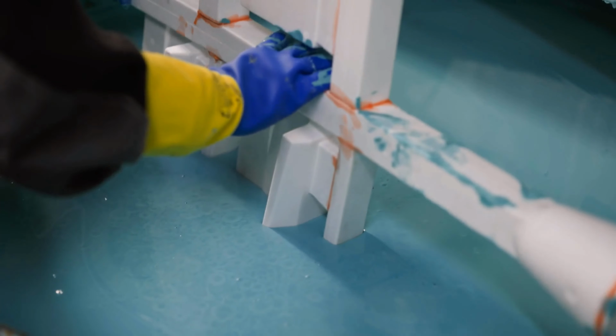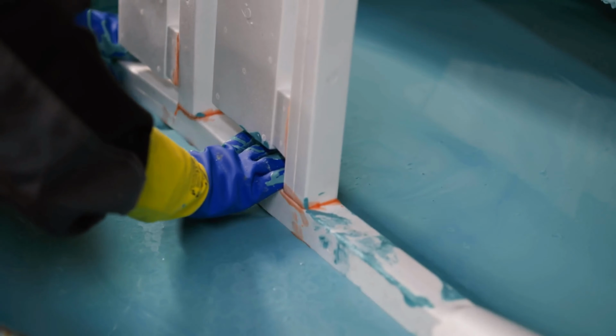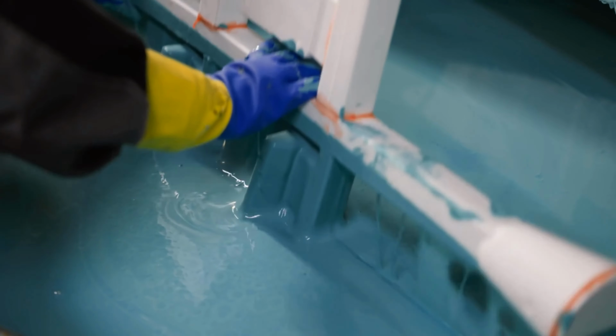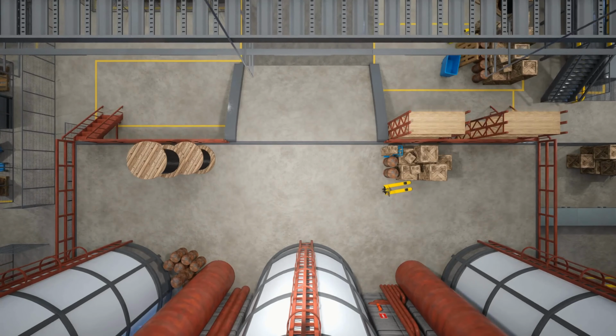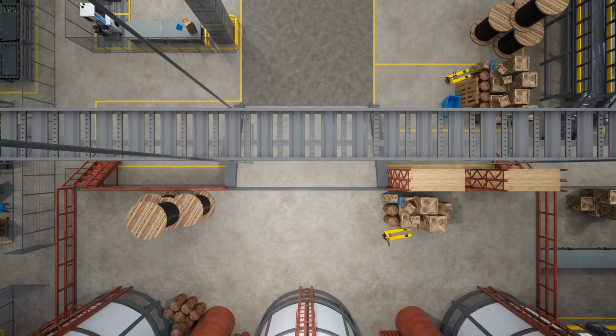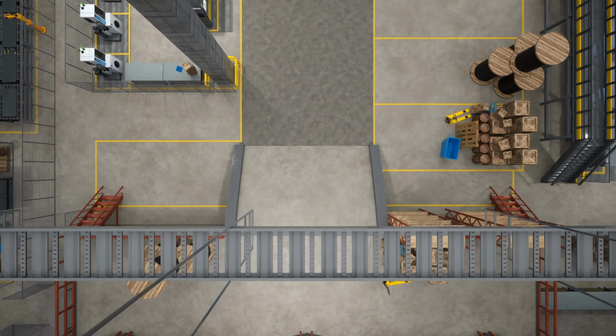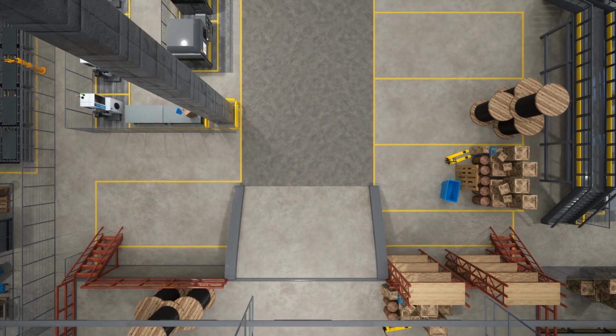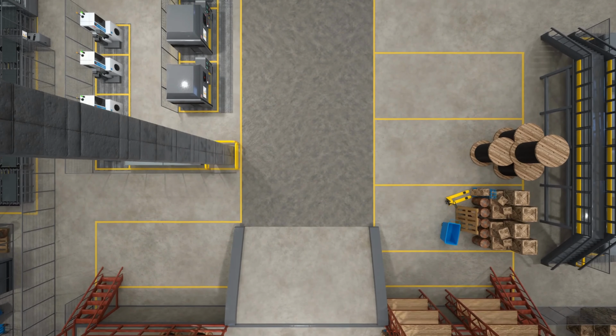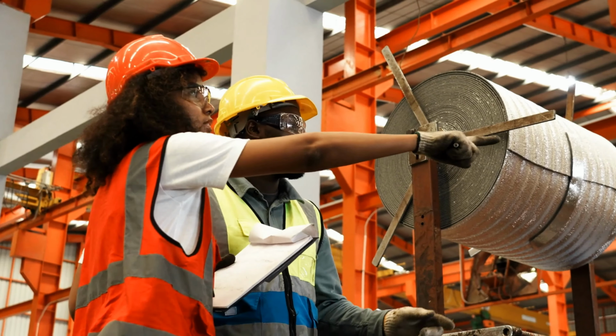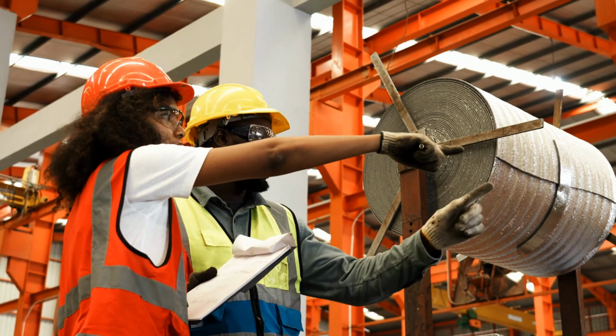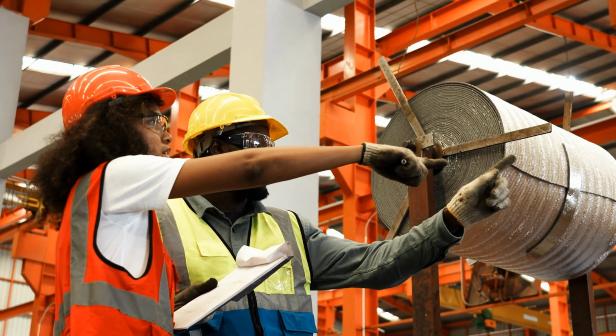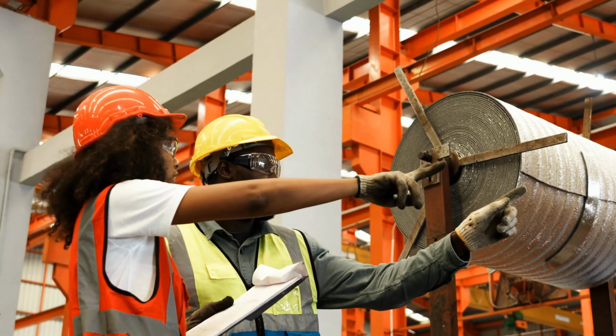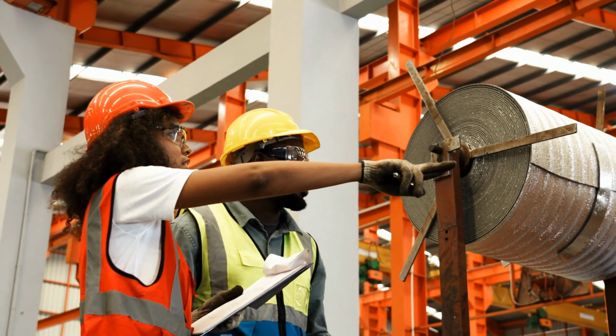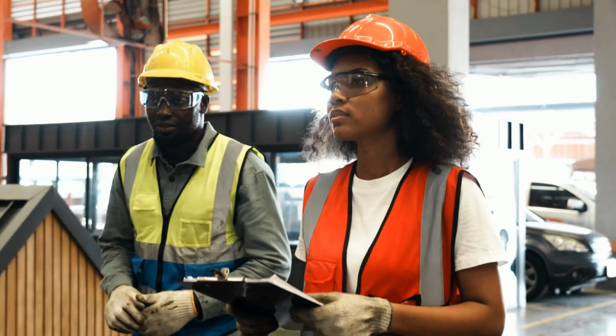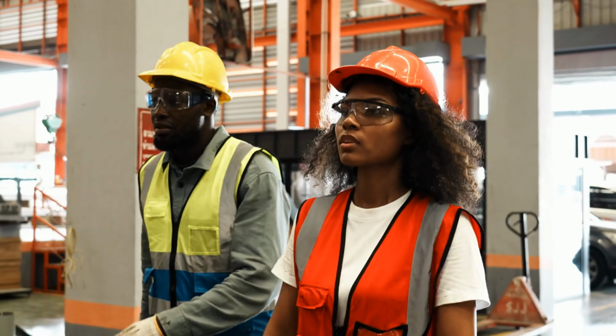2. Effects of an arc flash. Extreme heat: temperatures can reach up to 35,000 degrees Fahrenheit, 19,400 degrees Celsius, hotter than the surface of the sun. Blinding light: intense flashes can cause temporary or permanent vision damage. Pressure waves: the explosion generates a powerful blast that can throw people or objects. Flying debris: molten metal and shrapnel can cause severe injuries. Fire hazards: arc flashes can ignite nearby flammable materials, leading to secondary fires.